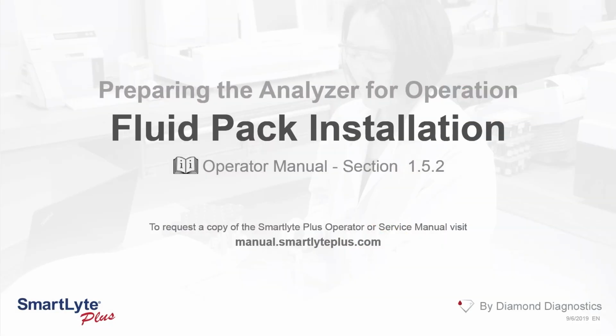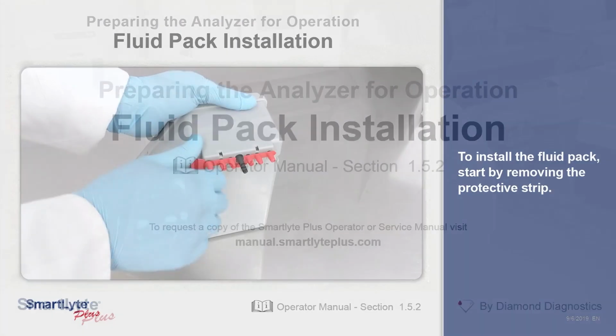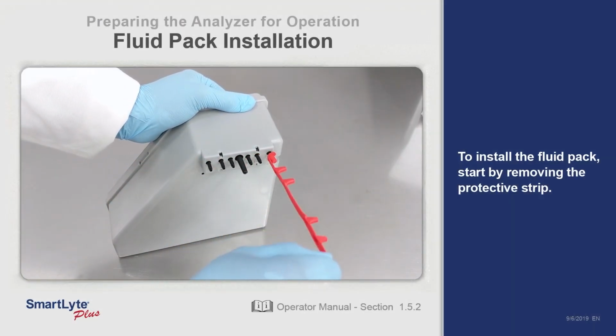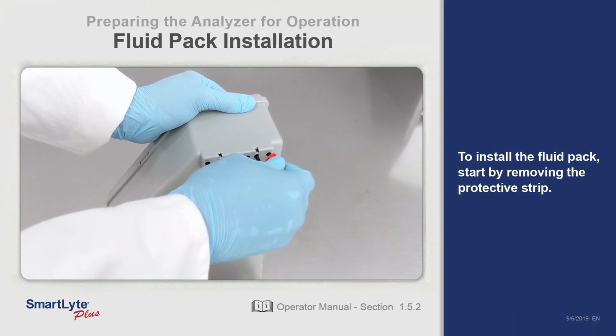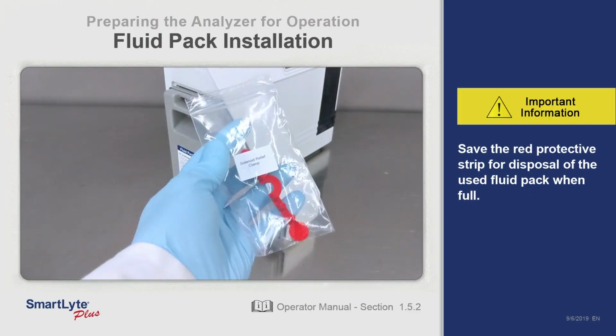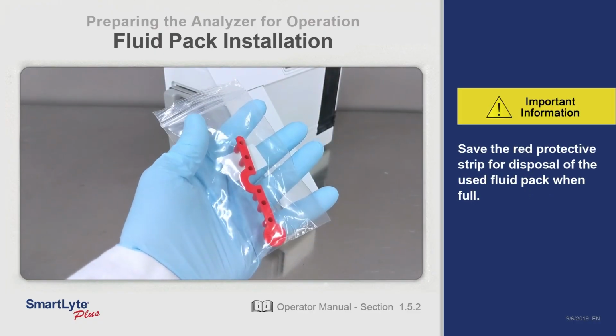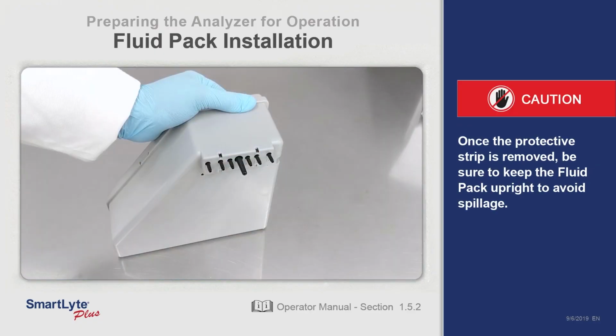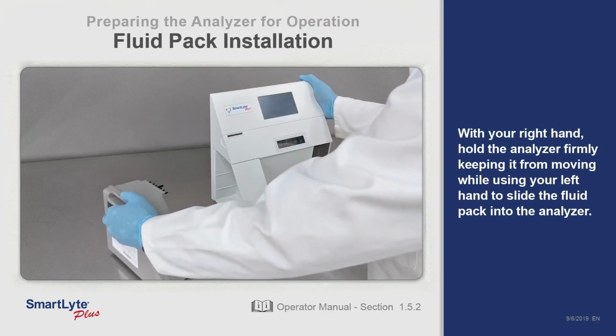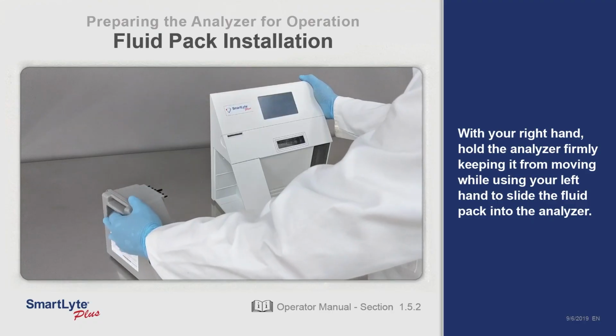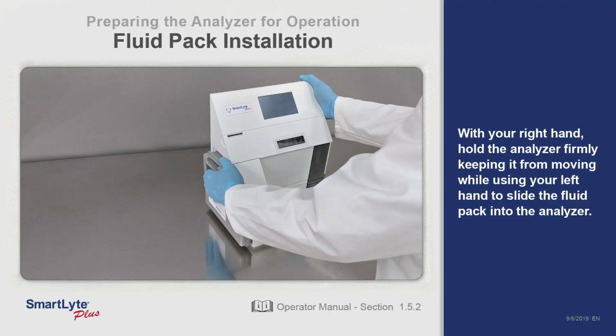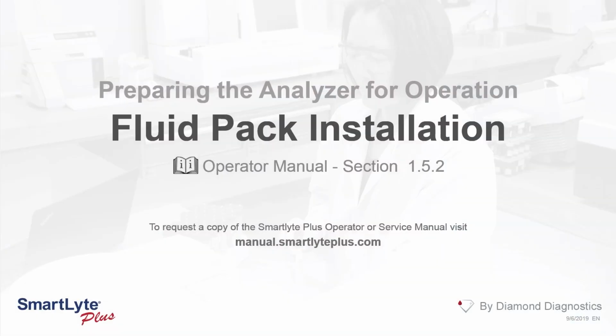Installing the fluid pack on the SmartLyte Plus. To install the fluid pack, start by removing the protective strip. Save the red protective strip for disposal of the used fluid pack when full. Once the protective strip is removed, be sure to keep the fluid pack upright to avoid spillage. To install the fluid pack, with your right hand, hold the analyzer firmly, keeping it from moving, while using your left hand to slide the fluid pack into the analyzer.